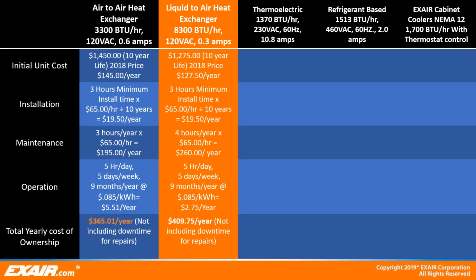Again, we're talking about the cost. The upfront purchase price for this unit was $1,275. Spread that over the manufacturer's expected service lifetime of 10 years, we come up with $127.50 per year. Using 3 hours as the minimum to install and a service rate of $65, spreading that over the manufacturer's expected service lifetime of 10 years, we come up with $19.50. Using 4 hours as the minimum for yearly maintenance and a service rate of $65, we have a yearly cost of $260 per year.